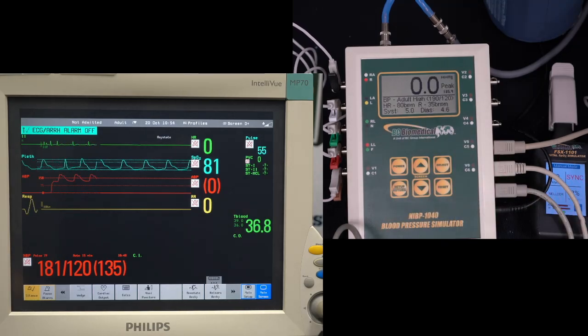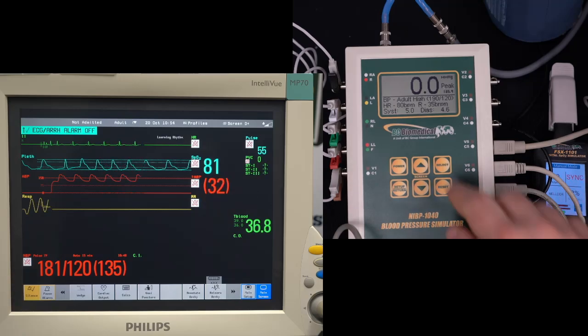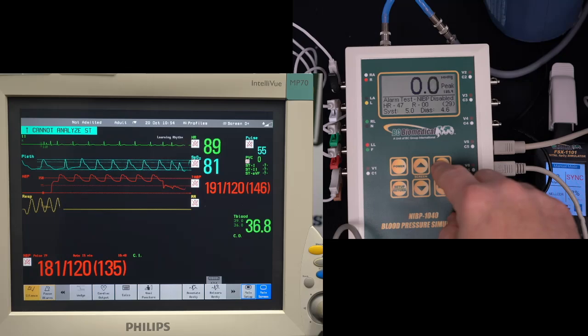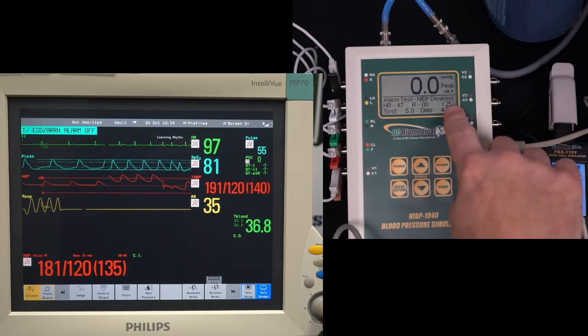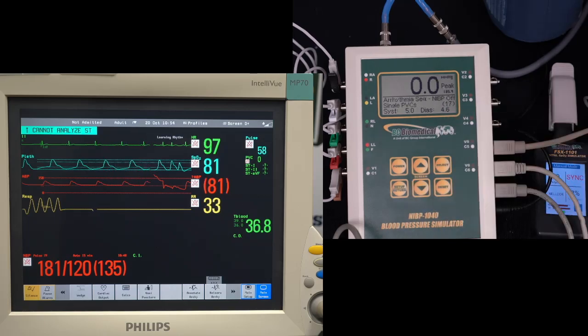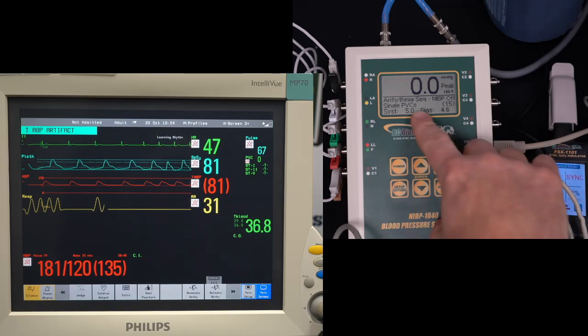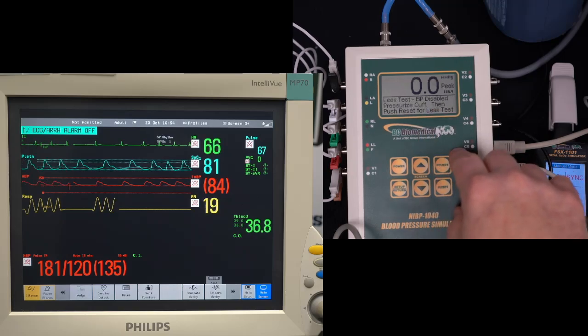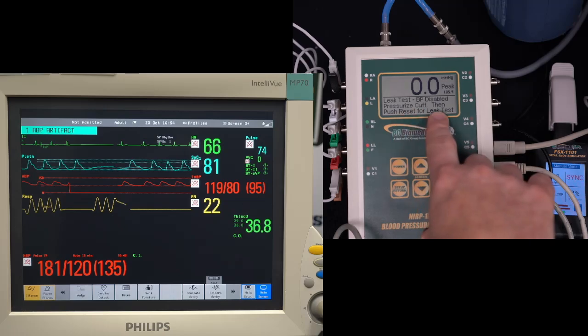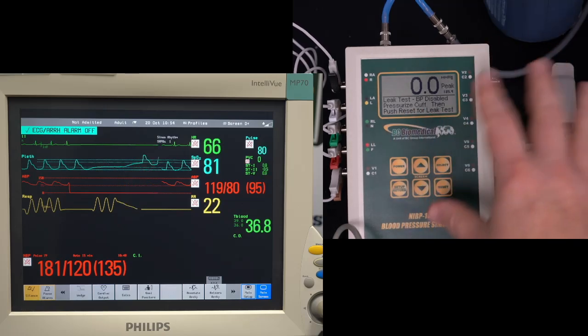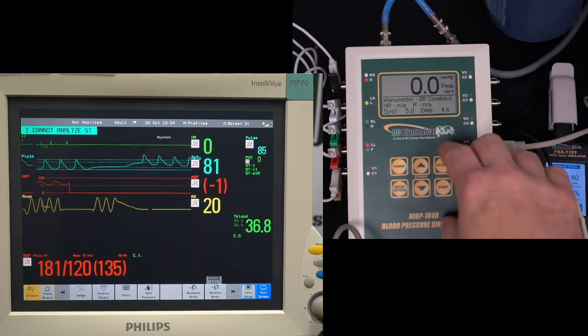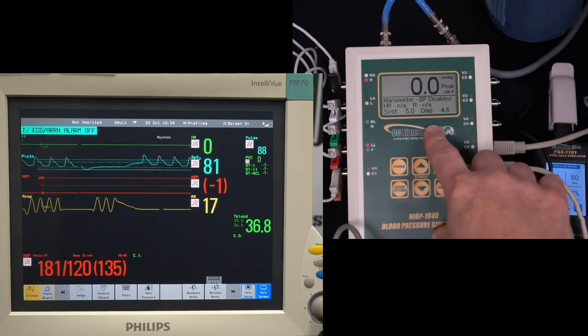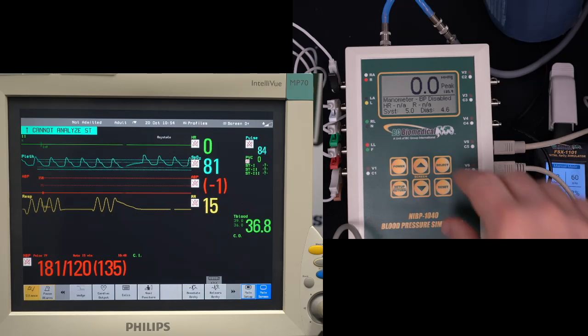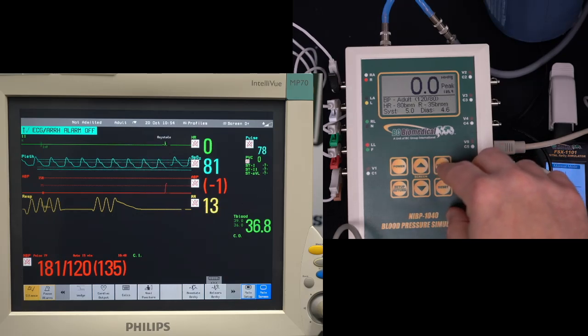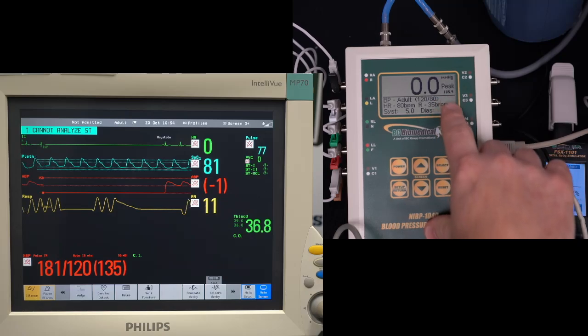So that's all the main features on the NIBP. We also have other test modes. There's a natal mode. There's an alarm test where it will automatically cycle through alarms for testing alarms on the monitor. We can step through arrhythmia sequences. We can also do a leak test. It'll tell you how much the cuff pressure drops over time. And we also have a manometer mode just for getting pressure readings. Now, the other thing in here is this peak.